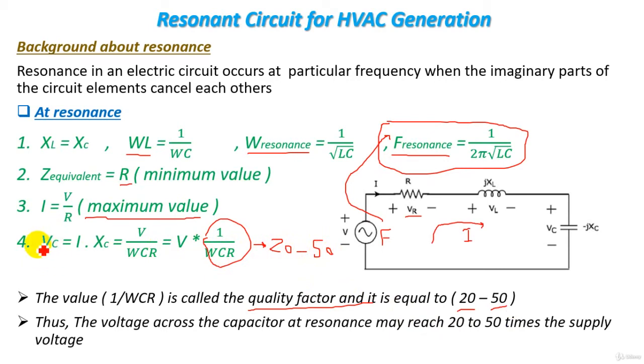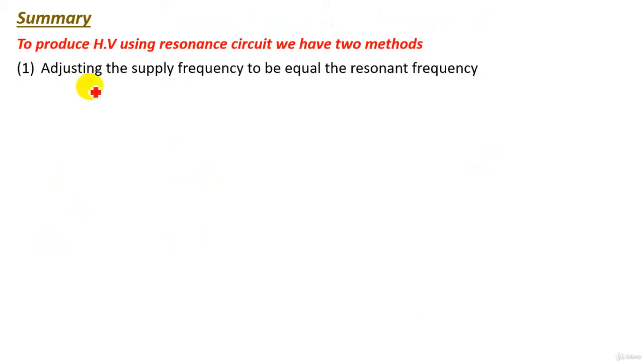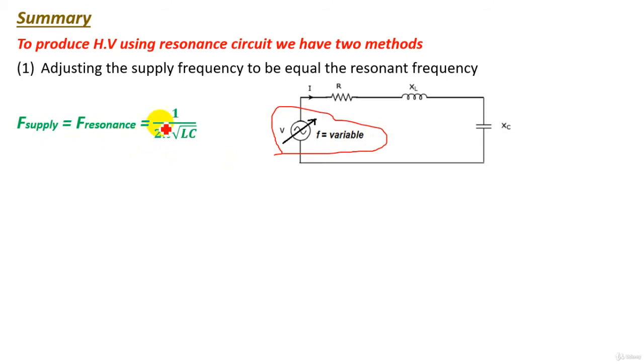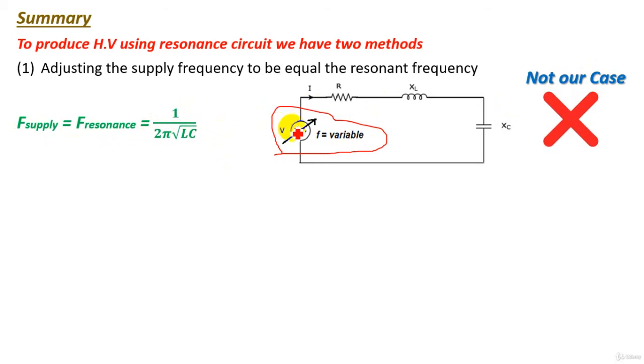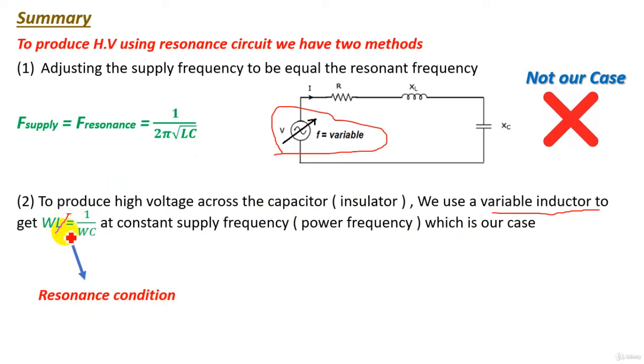In our high-voltage lab, the capacitor represents the insulator. To produce high voltage using a resonance circuit, we have two methods. The first is adjusting the supply frequency to equal the resonance frequency 1/2π√(LC). However, since we want to generate high-voltage AC at power frequency with a constant supply frequency of 50 or 60 Hz, we go to the second method: using a variable inductor and adjusting L to make ωL equal 1/ωC at constant power frequency.